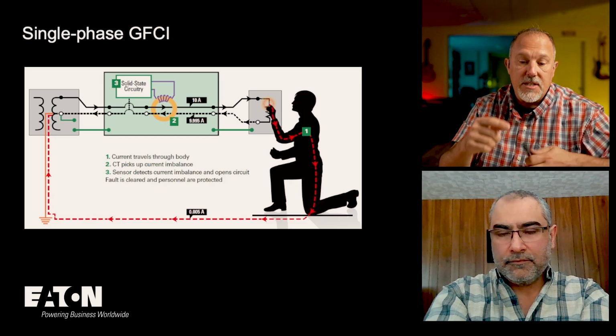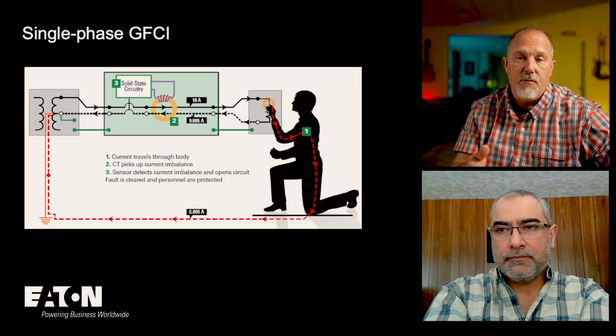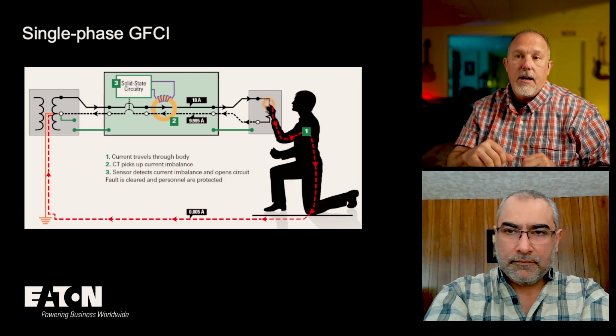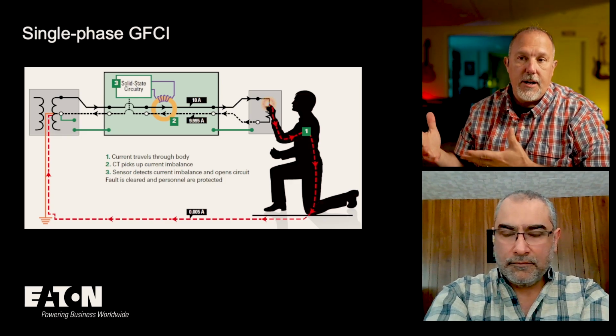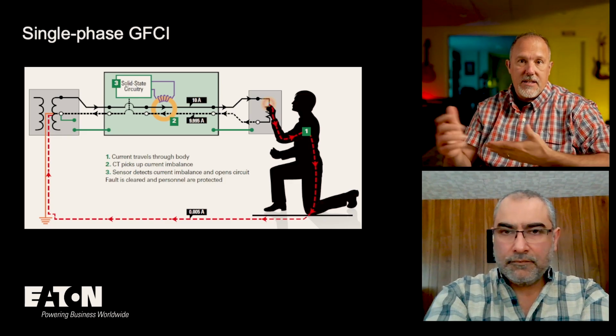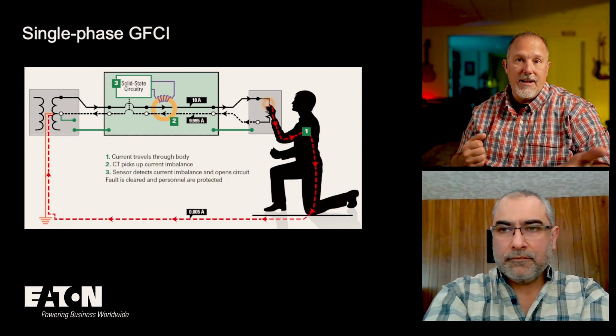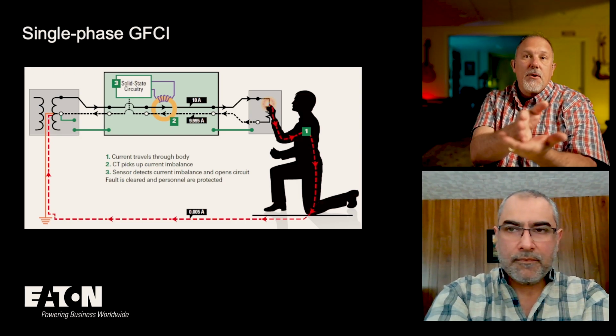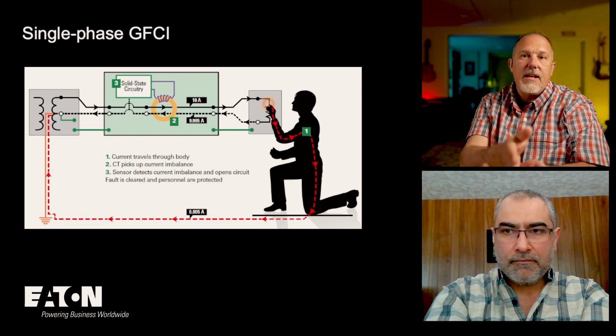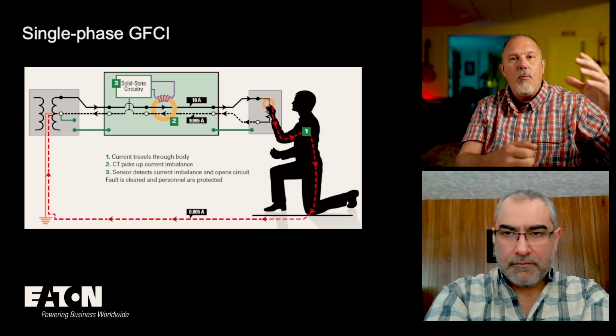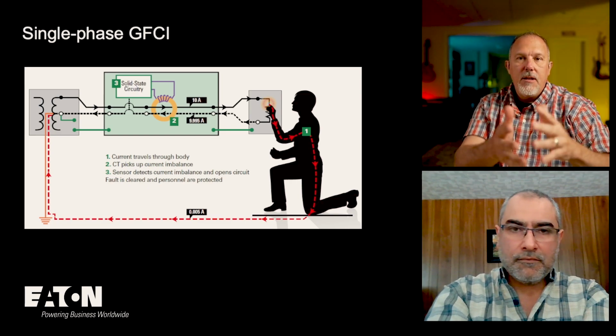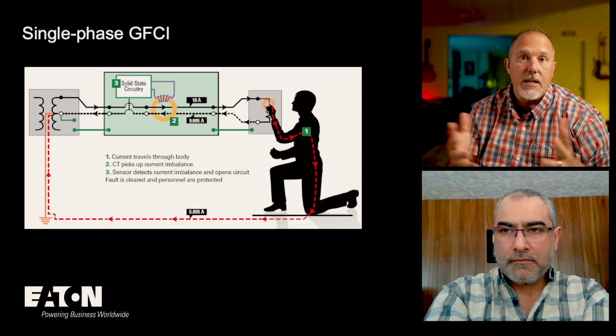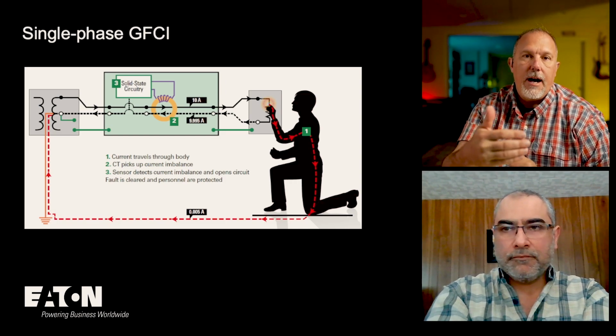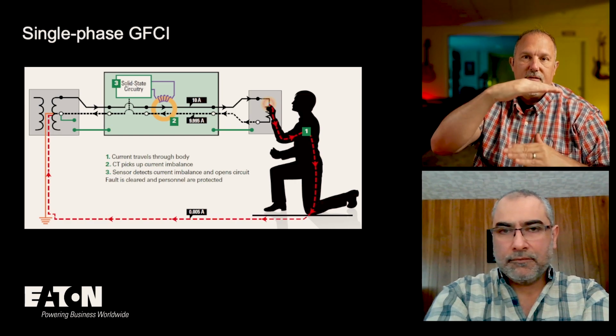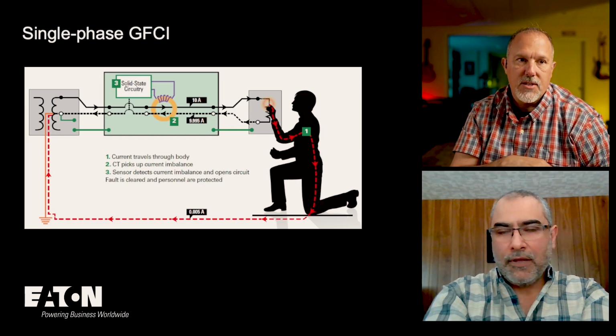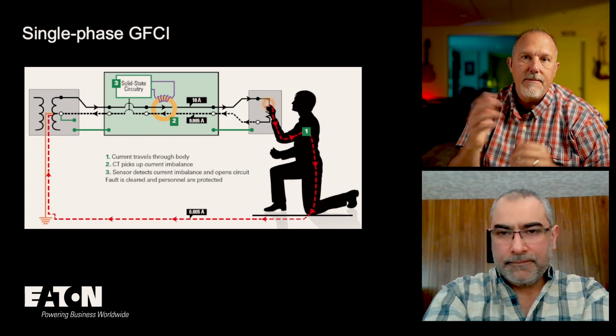I think that's where the basic discussion of the 50 volt threshold comes from - how much voltage do you need to drive through the body? We have a specific ohmic value of what we perceive as the impedance of the body, and to your point earlier, that's a moving target. But we pick a number and say, if I'm going to say it's 400 ohms, what voltage do I need to get me around 4 to 6 milliamps?